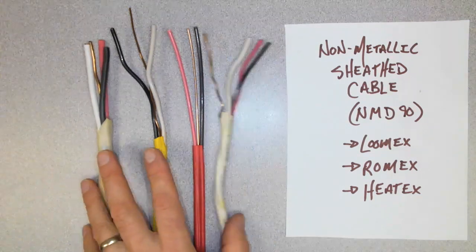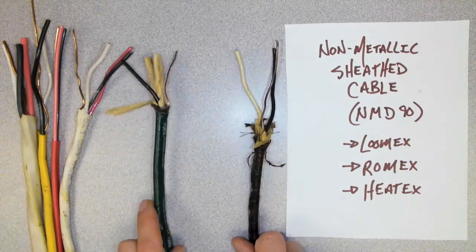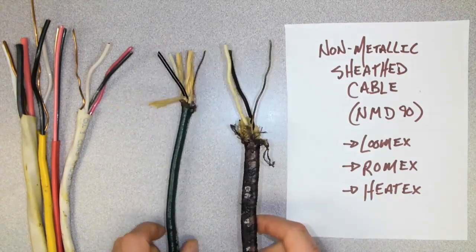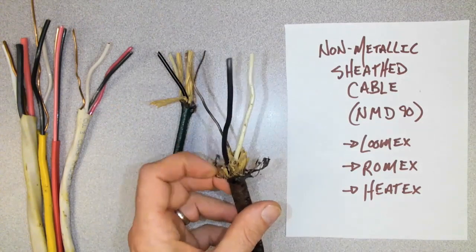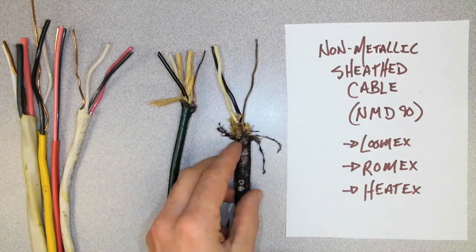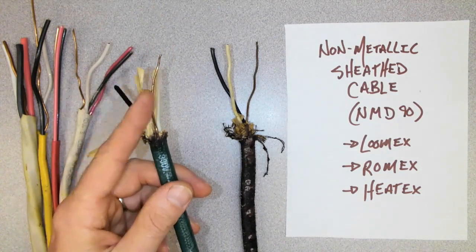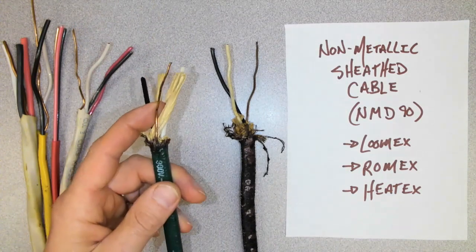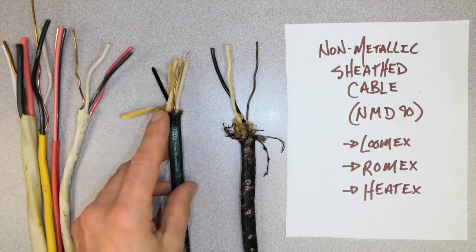Now, in the past, there has been some really old, archaic types of wiring like this that have a fibrous sort of tar jacket around the outside, and they have paper in there, which is somewhat flammable. And on the really old stuff, you'll notice that the bonding conductors are actually non-existent or smaller than standard. This one is from the 1950s, and the bond is a 16-gauge bare copper wire. All of these cables are found in the residential sector of the electrical industry.